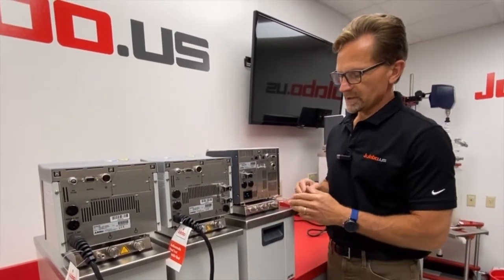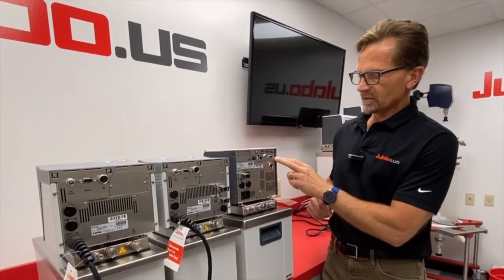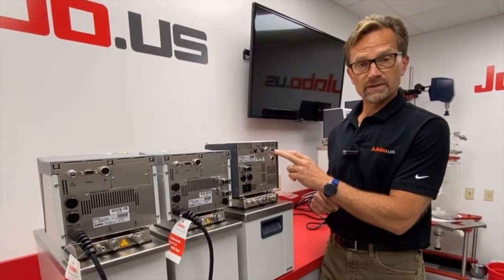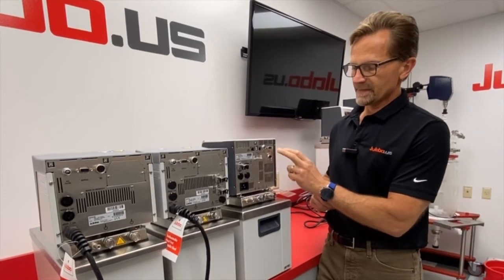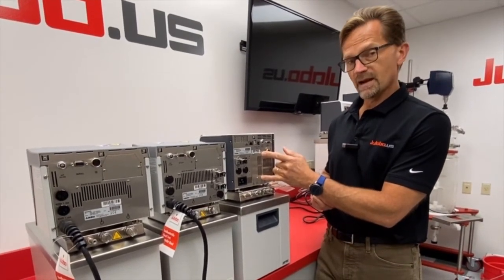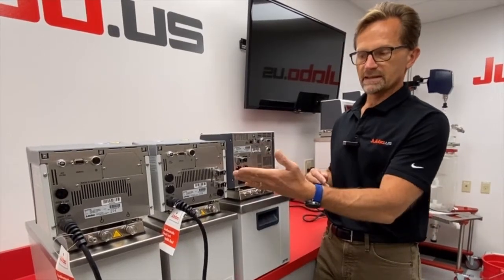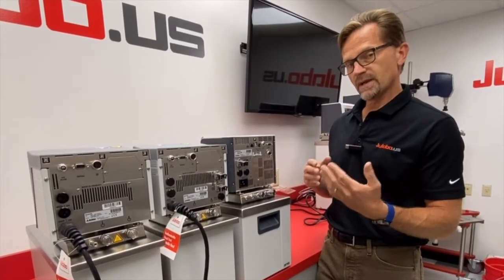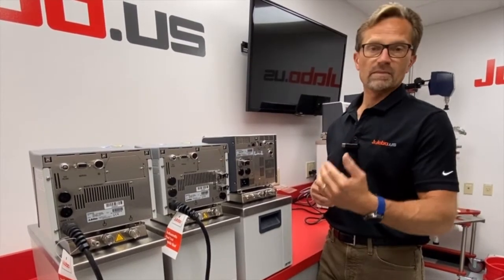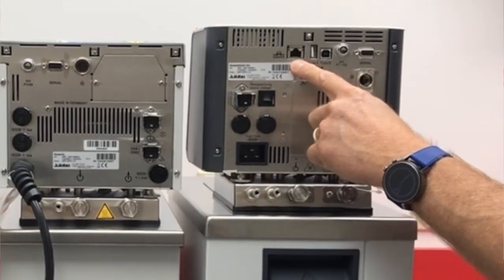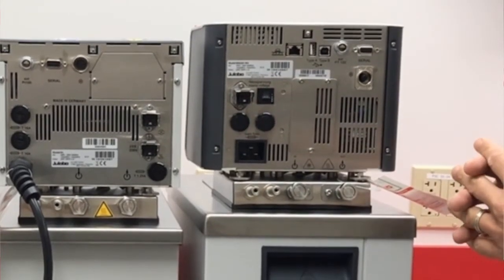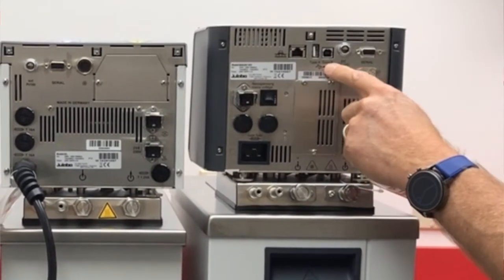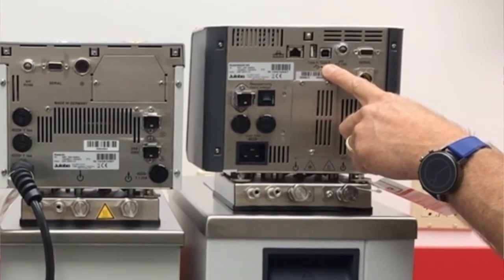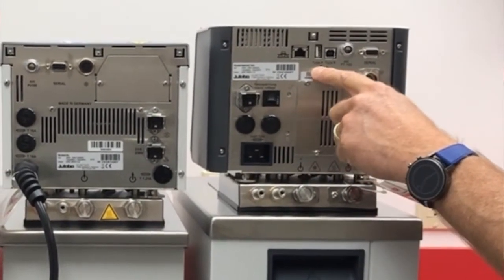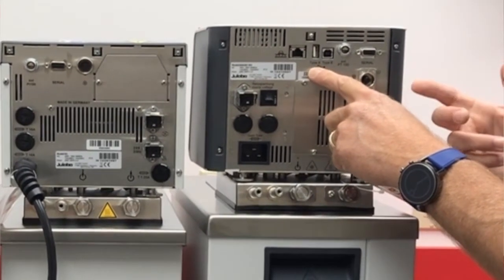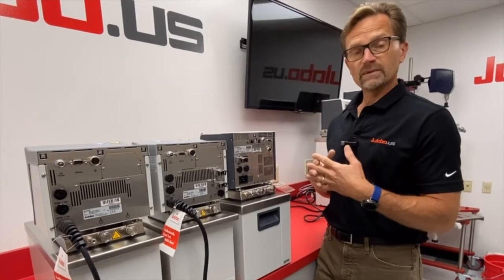If we move on to the MAGIO MX, you'll see that we have a serial port. It has both RS-232 and RS-485 capability. We have an optional slot here for your analog module as well. So those are both similar to the SL model. But the MAGIO MX incorporates a lot more modern communication capabilities with Ethernet port, Modbus, TCP/IP is integrated. We also have a USB Type B port for communication directly to a PC, and a USB Type A slot, so you can actually do data recording on the system directly with a USB device.